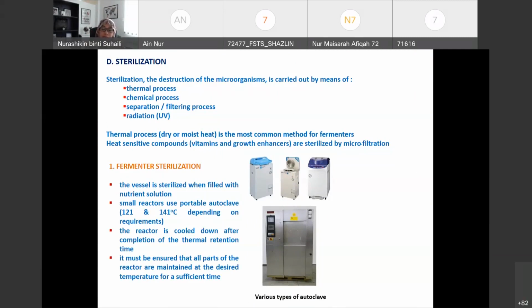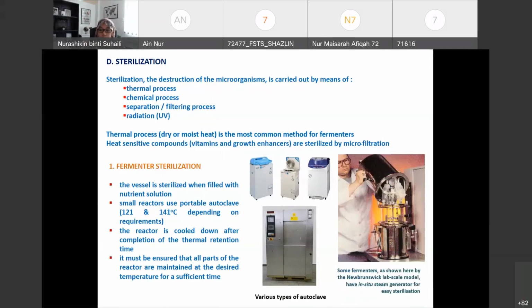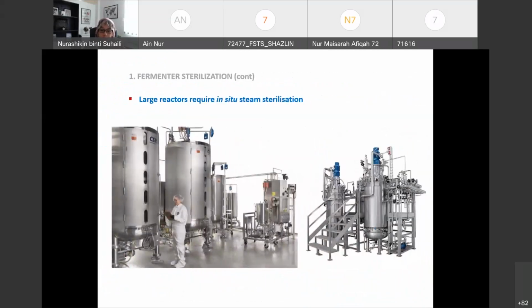But for more than a 10 liter fermenter, you have to use in situ sterilization. You don't use an autoclave anymore. For example, big bioreactors like this require in situ sterilization. In situ means that this bioreactor is connected to a steam system, whereby the steam will go through the bioreactor and it will be sterilized in place. That's why it's called in situ. We don't require an autoclave anymore for large scale bioreactors. So there are two types of sterilization: autoclave for small scale bioreactors, and in situ steam sterilization for large bioreactors.